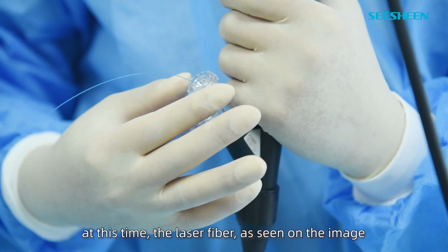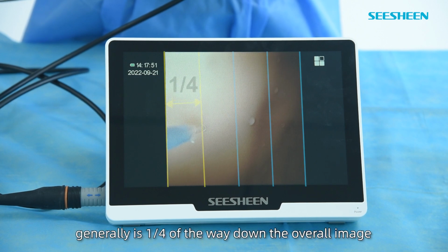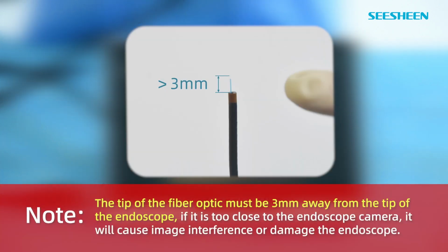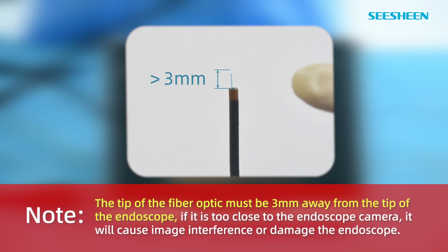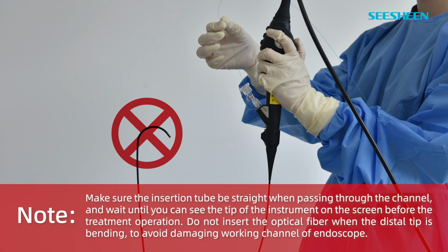At this time, the laser fiber, as seen on the image, is generally 1/4 of the way down the overall image. Note: the tip of the fiber optic must be 3 mm away from the tip of the endoscope. If it is too close to the endoscope camera, it will cause image interference or damage the endoscope. Make sure the insertion tube is straight when passing through the channel, and wait until you can see the tip of the instrument on the screen before the treatment operation. Do not insert the optical fiber when the distal tip is bending to avoid damaging the working channel of the endoscope.